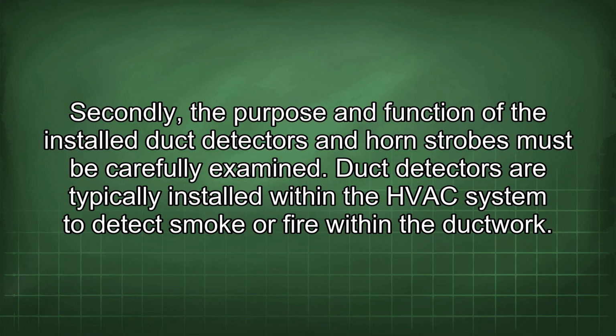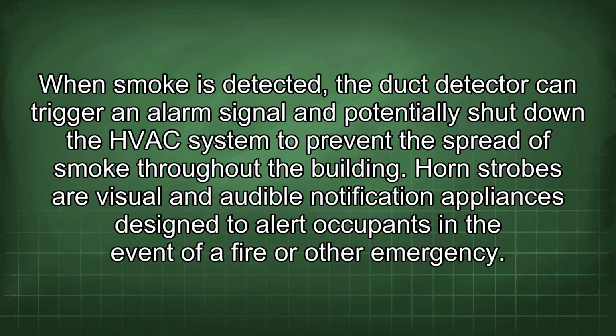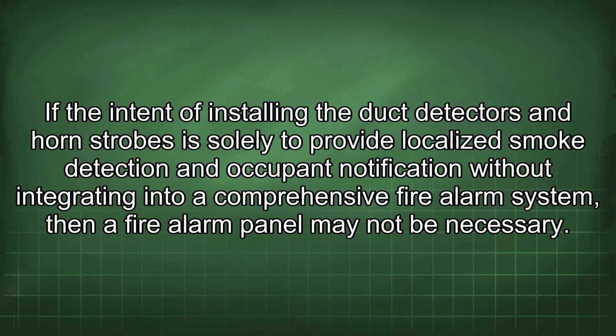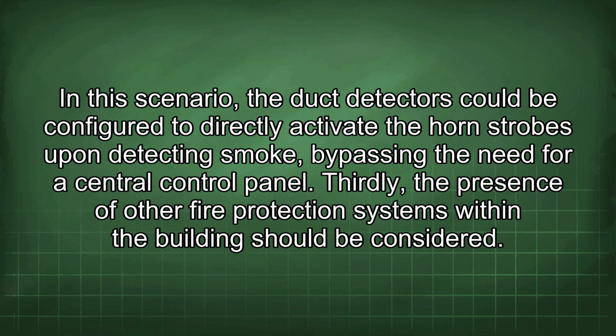Secondly, the purpose and function of the installed duct detectors and horn strobes must be carefully examined. Duct detectors are typically installed within the HVAC system to detect smoke or fire within the ductwork. When smoke is detected, the duct detector can trigger an alarm signal and potentially shut down the HVAC system to prevent the spread of smoke throughout the building. Horn strobes are visual and audible notification appliances designed to alert occupants in the event of a fire or other emergency. If the intent of installing the duct detectors and horn strobes is solely to provide localized smoke detection and occupant notification without integrating into a comprehensive fire alarm system, then a fire alarm panel may not be necessary. In this scenario, the duct detectors could be configured to directly activate the horn strobes upon detecting smoke, bypassing the need for a central control panel.